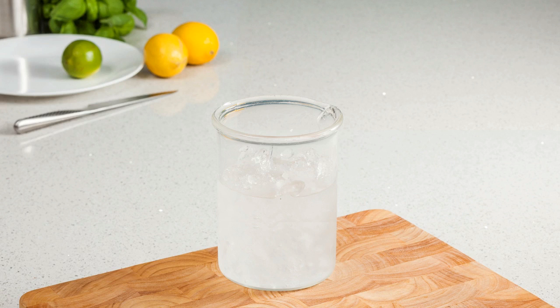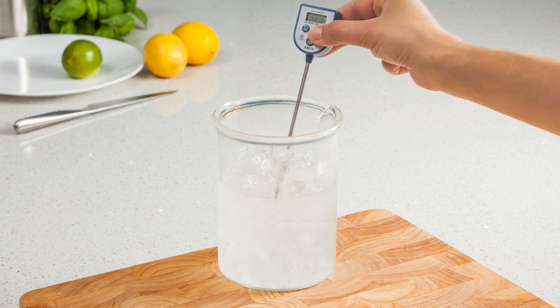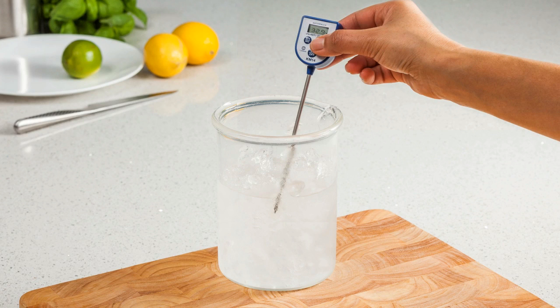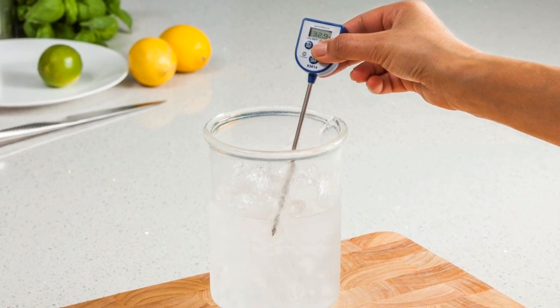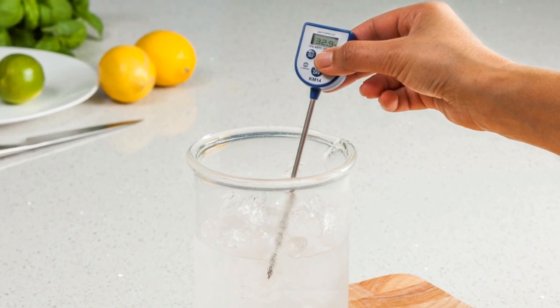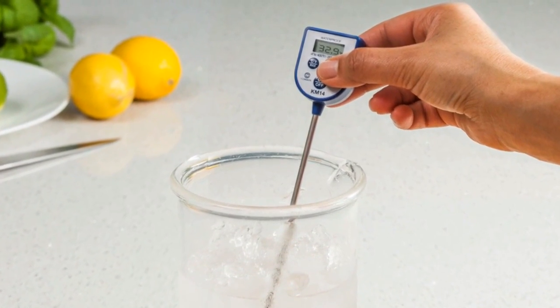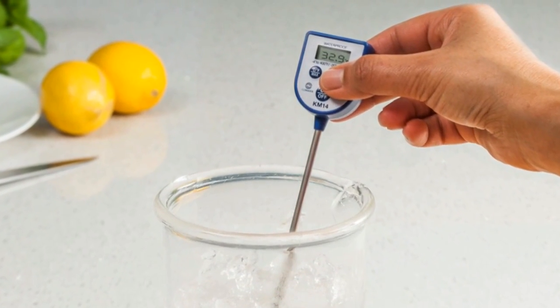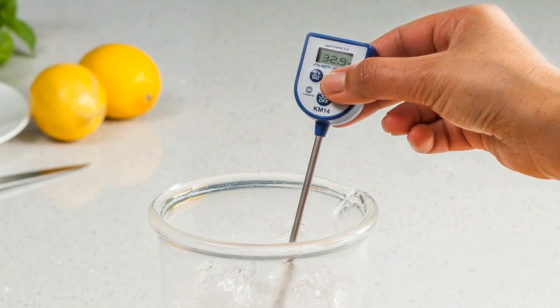To start the calibration check, simply immerse the probe of your thermometer into the solution so that it's at least 2.5 centimeters or 1 inch below the level of the water in the crushed ice solution. You should not allow the probe tip to rest on the bottom or the sides of the container. Now you need to wait for the reading on your thermometer to become stable. We would normally expect a reading to show that is within 1 degree of 0 degrees Celsius or within 2 degrees of 32 degrees Fahrenheit.